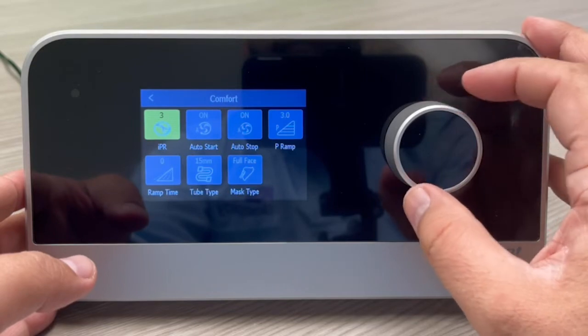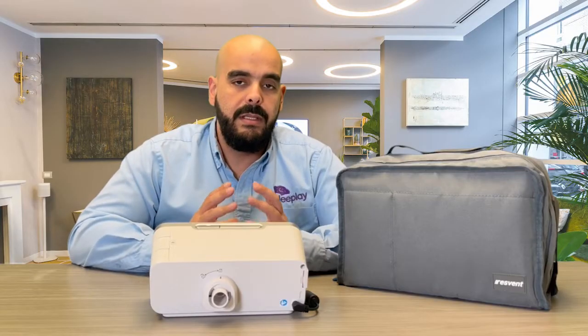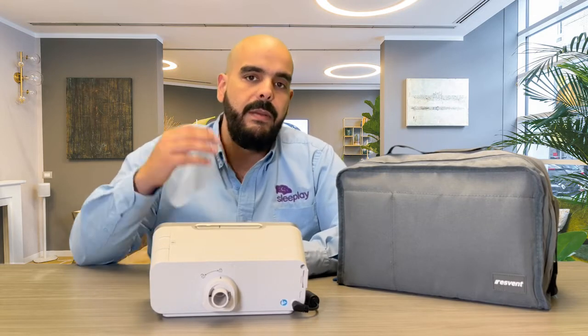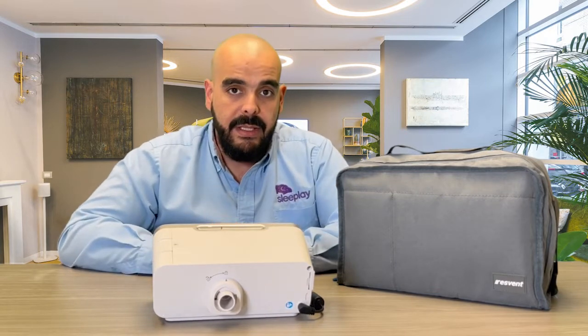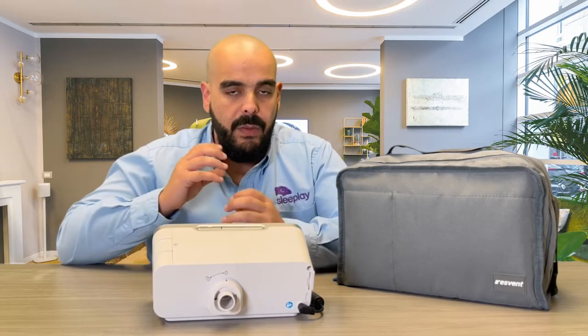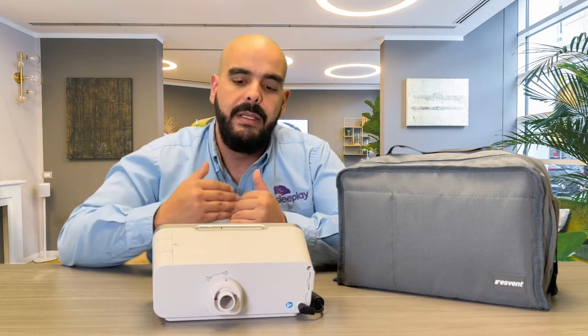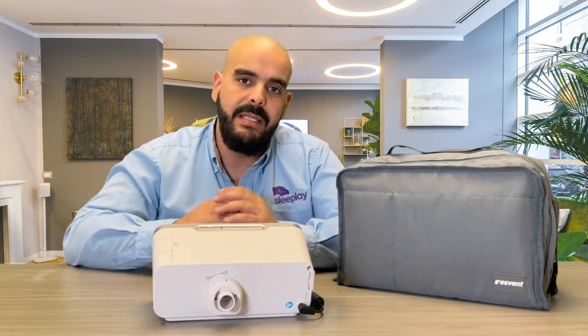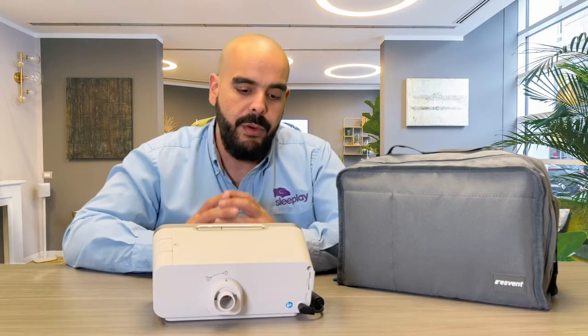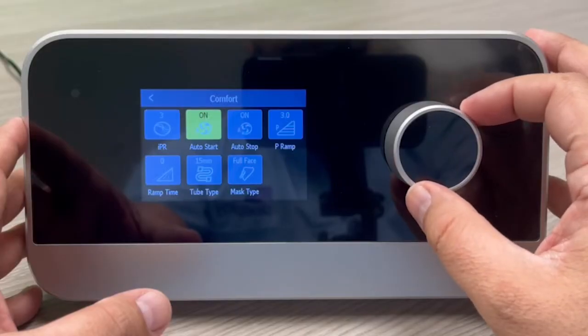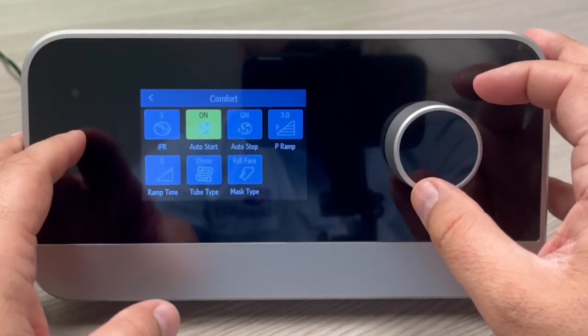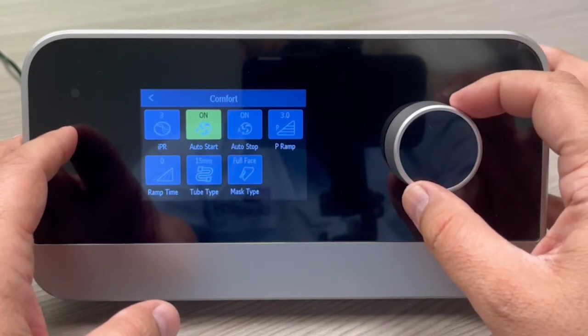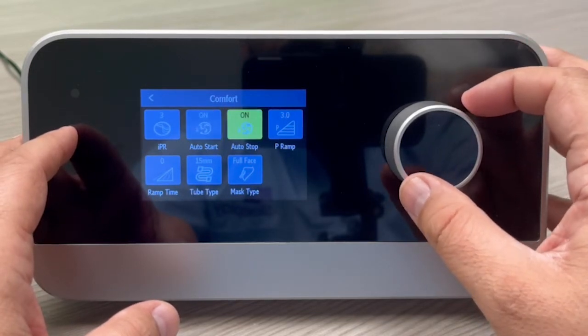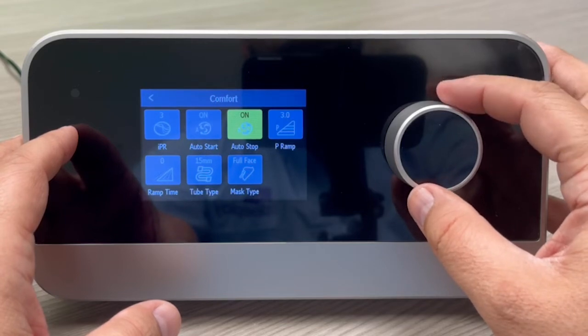When you select there, you have IPR, which stands for Intelligent Pressure Relief. Now, this is similar to EPR and C-Flex in other brands. What IPR does is it helps you exhale. When you're taking in the breath and you go to exhale, the machine relieves a little bit of pressure, so it's easier for you to exhale, making the therapy a little bit more comfortable for you. The next one over is the auto start. That's when you put the mask on and you breathe through the mask, the machine will turn on. Then the auto stop, which is when you take it off and it senses that the mask is off for a while, it'll shut off.